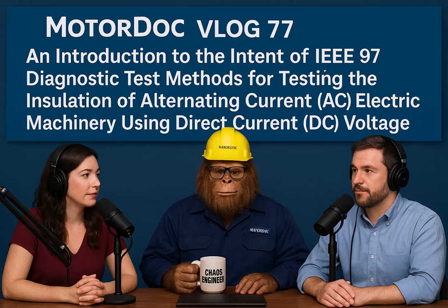The guide says this current is the key variable. Can you break down what actually makes up that total current you measure? Yeah, let's get into that. So when you apply that DC voltage, the total current isn't just one thing, it's actually a mix of different components, and they each behave differently over time. First up, you've got the capacitive current. Right, the initial inrush, like charging up a capacitor. Exactly like that. It's high magnitude, but it decays super rapidly, usually gone within a second or so.